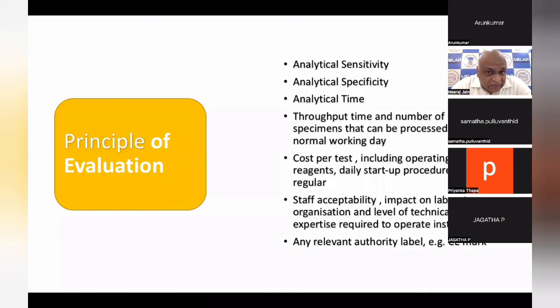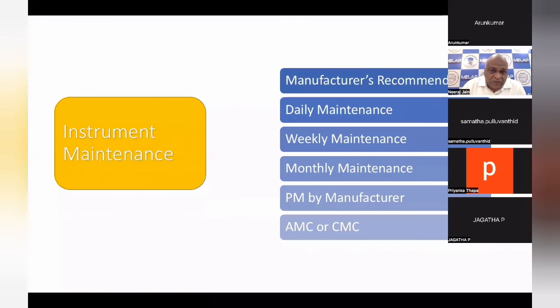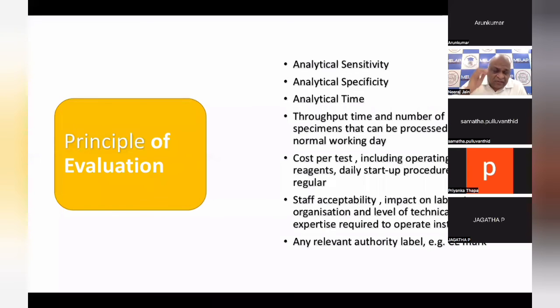Analytical sensitivity. Analytical sensitivity means what is the minimum difference a machine is able to appreciate. Previously, we were using this term for lower limit of quantification also. In this hematology analyzer, we are able to estimate 4 as the lowest value of hemoglobin, or 3. But nowadays, we call that lower limit of quantification.